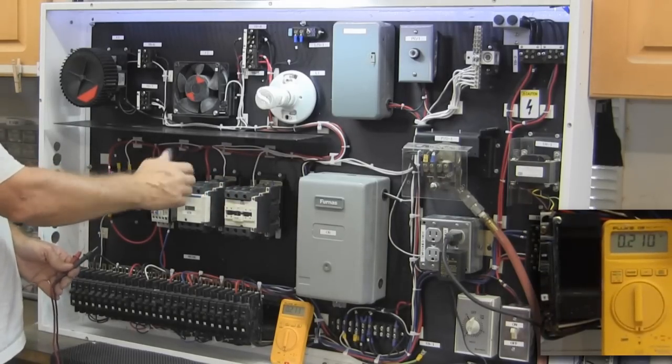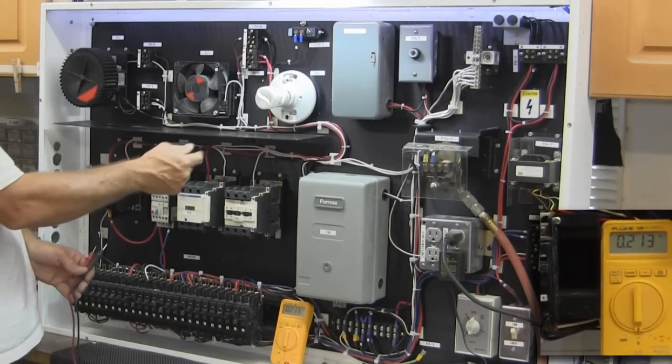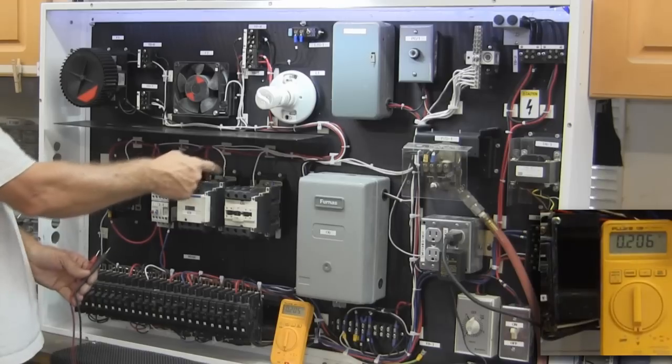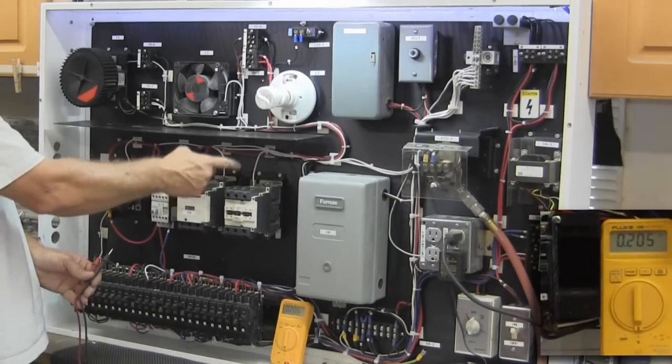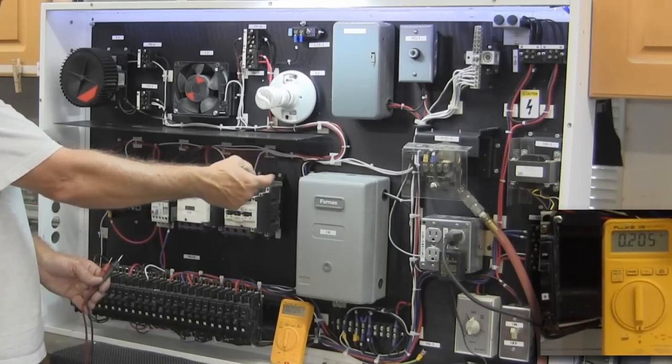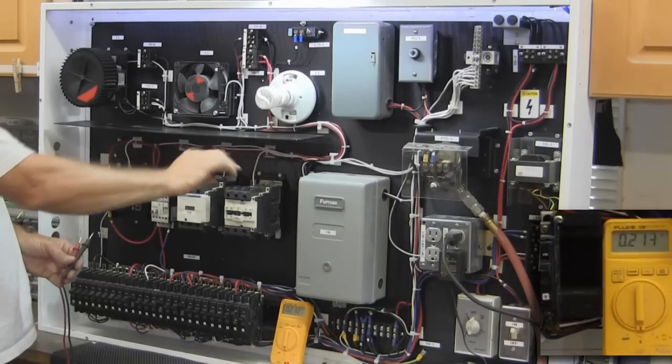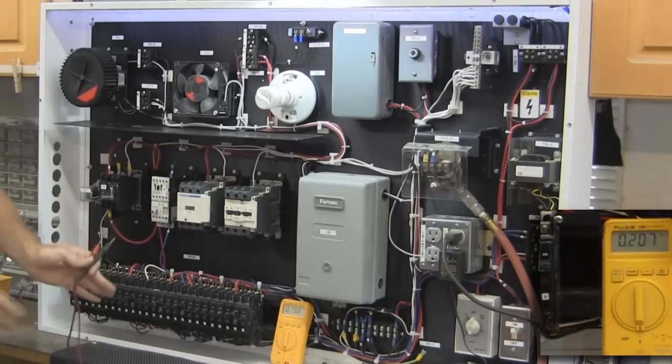On the left side, which is A1, I have the hot and on the A2, I have the neutral. This particular one, I have A1 is the neutral and A2 would be the switched hot. So it doesn't really matter what side of that coil goes on in a basic system.